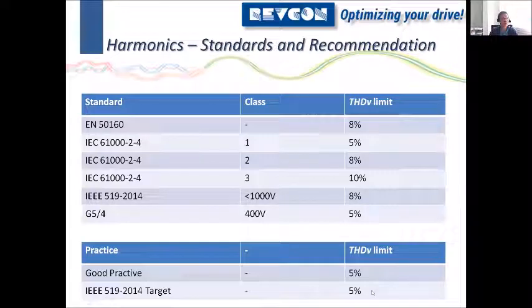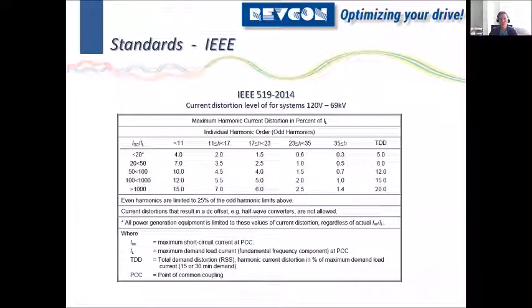So it's a little bit tricky to read because many people think we have an 8% limit. But if we follow the targets and the recommendation of the IEEE, our result on the main supply will be much better. So anyway, I think this is the most commonly used table for harmonic mitigation when we look at harmonic distortion. So for now, I want to explain the difference between TDD and THDI. And looking at the short circuit current ratio, we will do that later. But for now, we focus on the TDD and THDI.